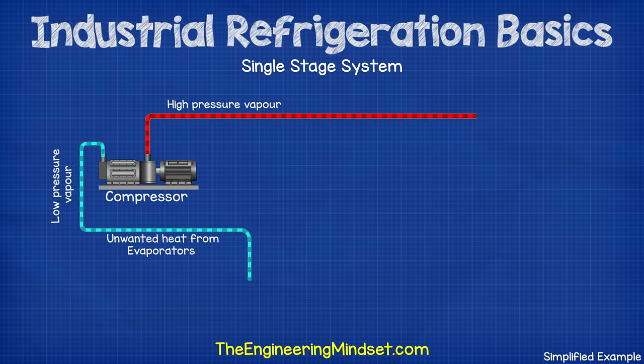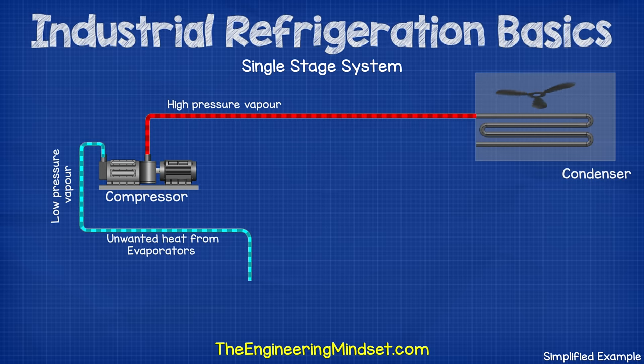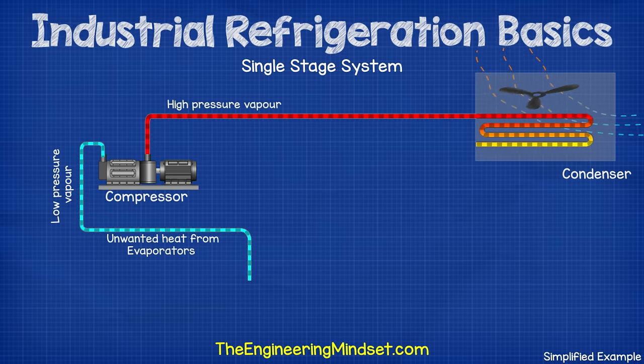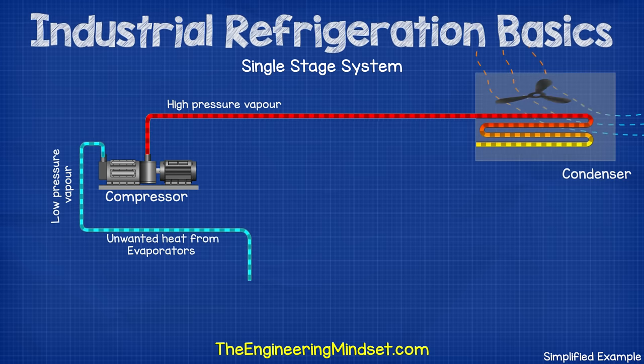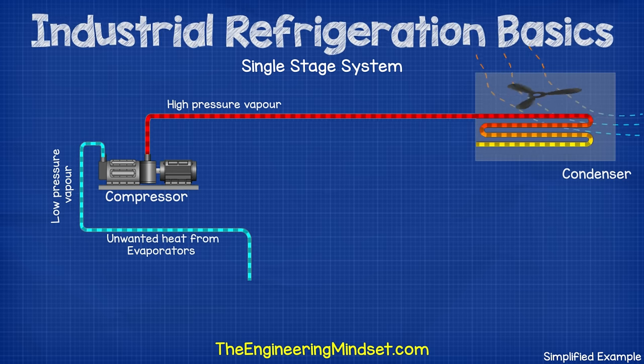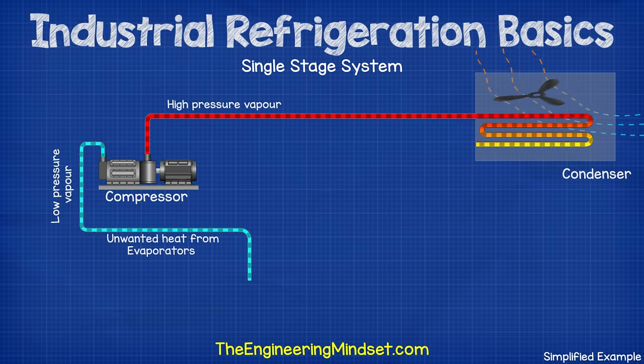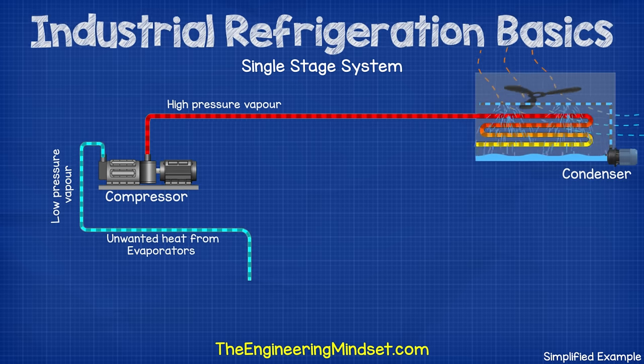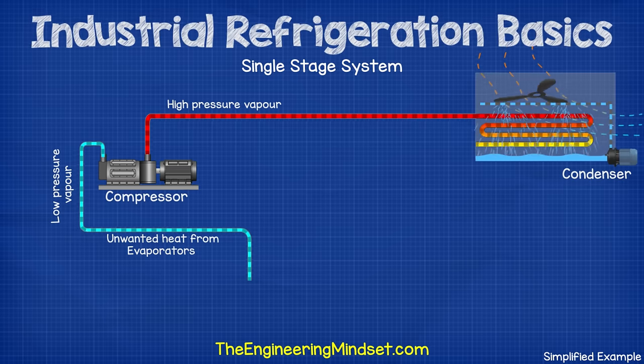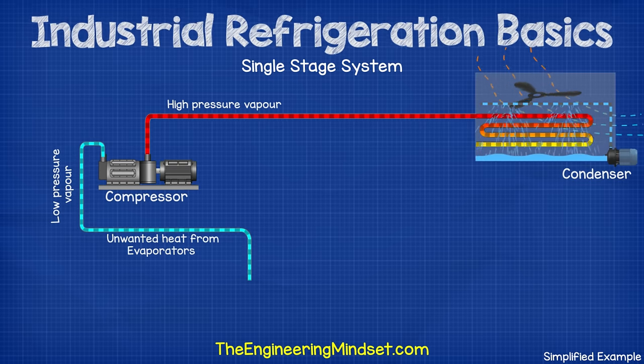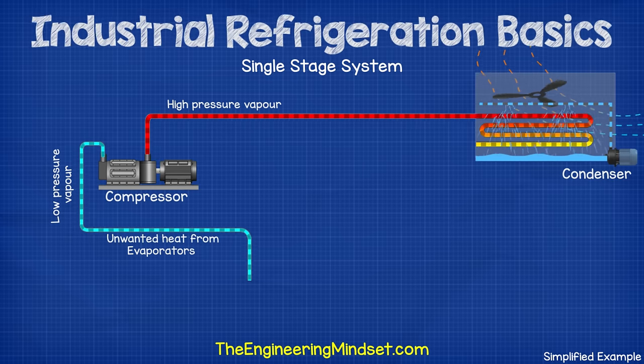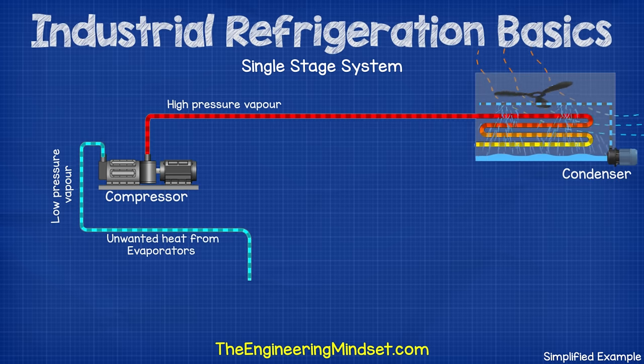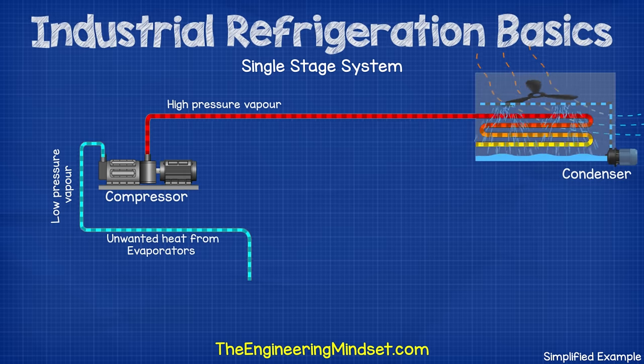The high pressure refrigerant vapor exits the compressor and flows to the condenser. The condenser cools the refrigerant down by pulling the unwanted heat out and discharging it into the ambient outside air. This is typically done by passing the hot refrigerant through the inside of some small tubes and using a fan to force the cooler ambient air across the outside of the tubes. We'll often find a small pump spraying water over the pipes as well — some of this will evaporate and help carry more heat away. The refrigerant is sealed inside the pipe and does not come into contact with the air or water; only the heat passes through the pipe wall.